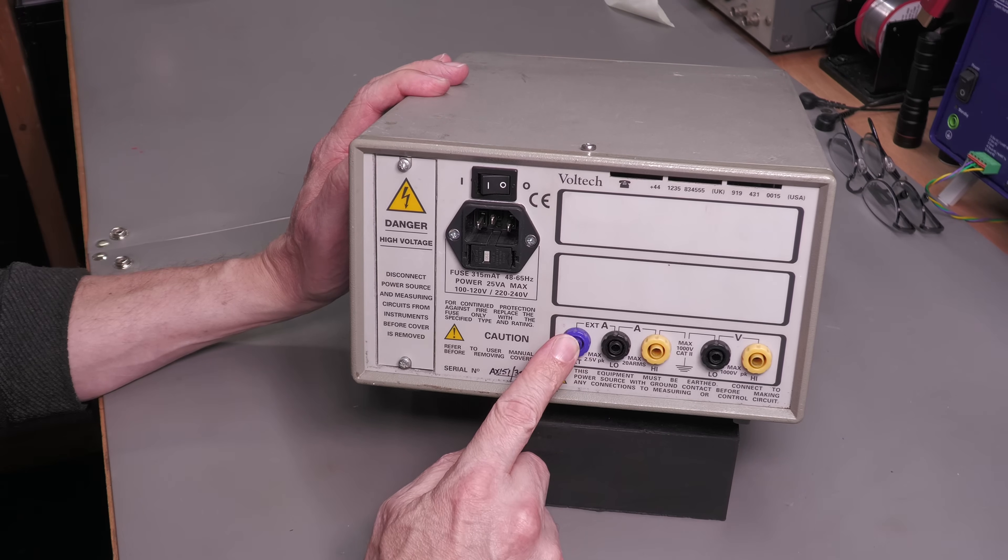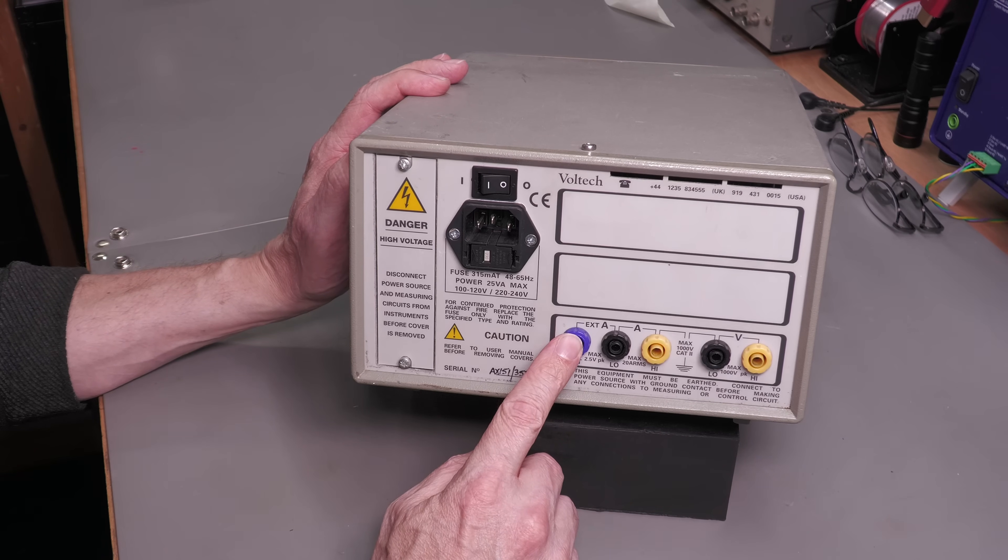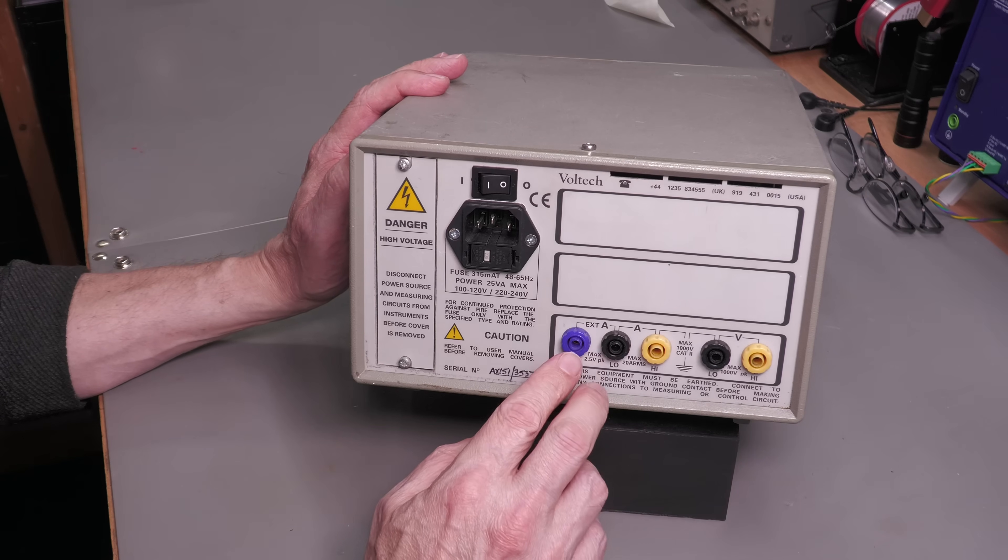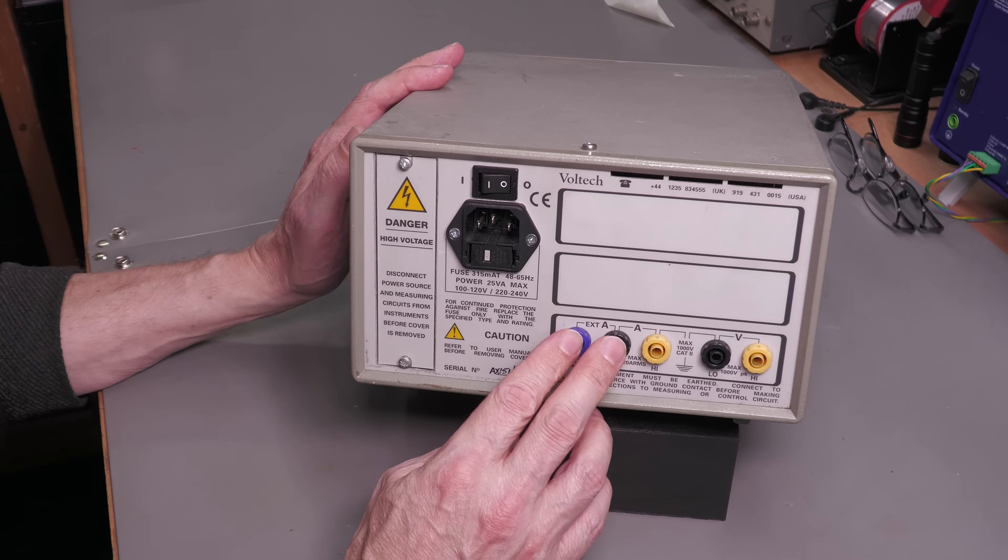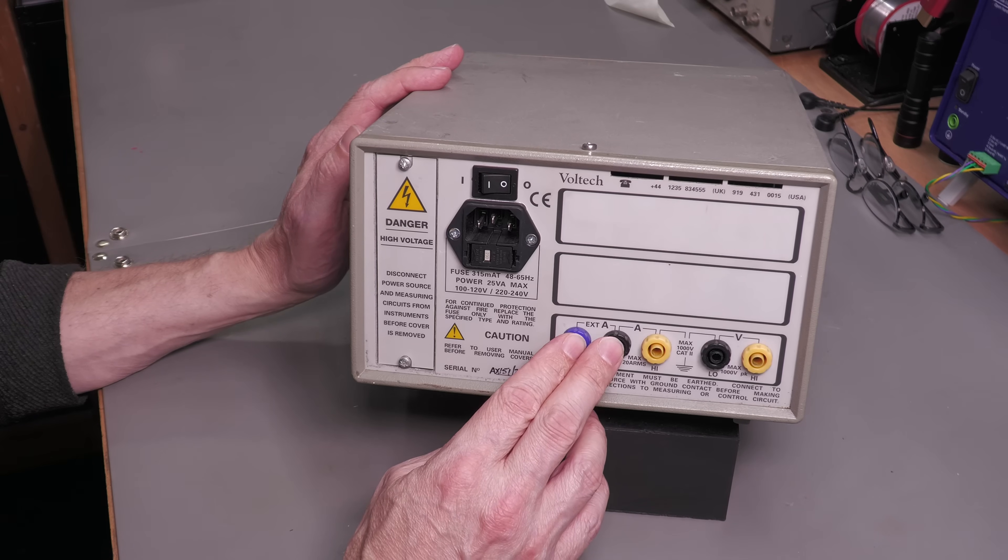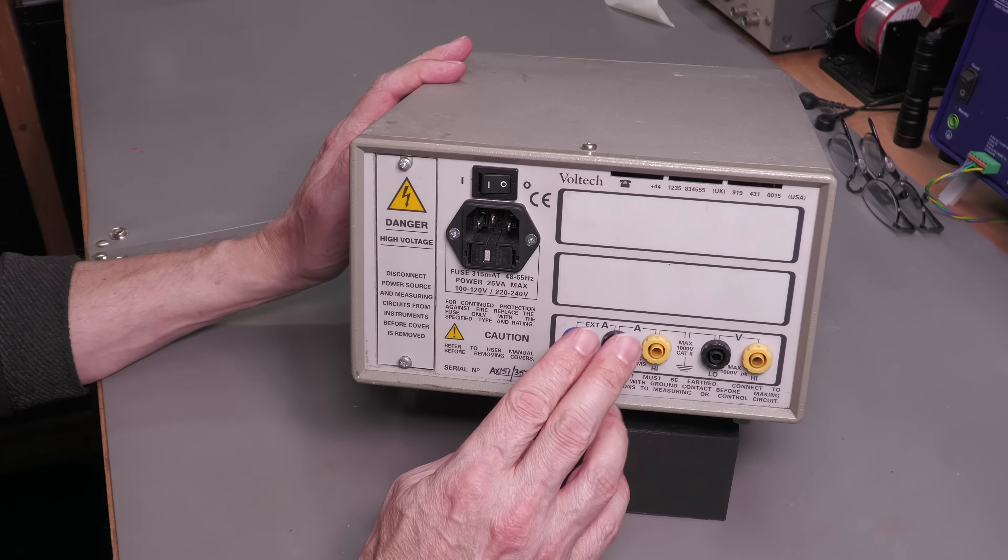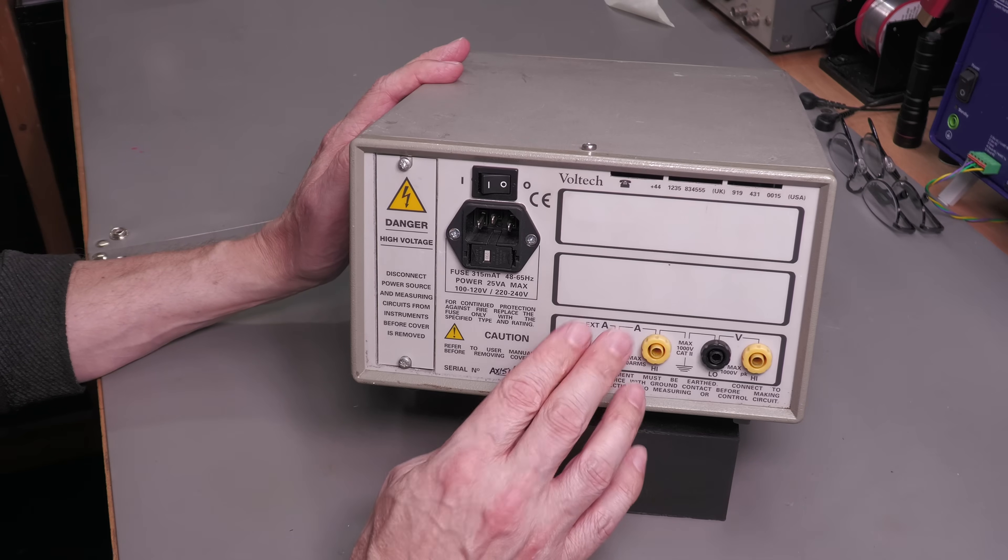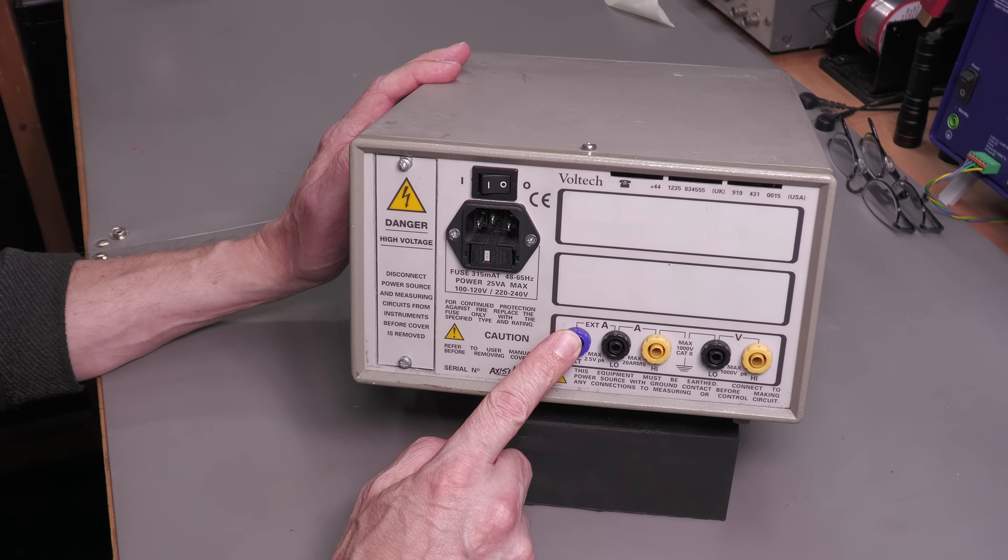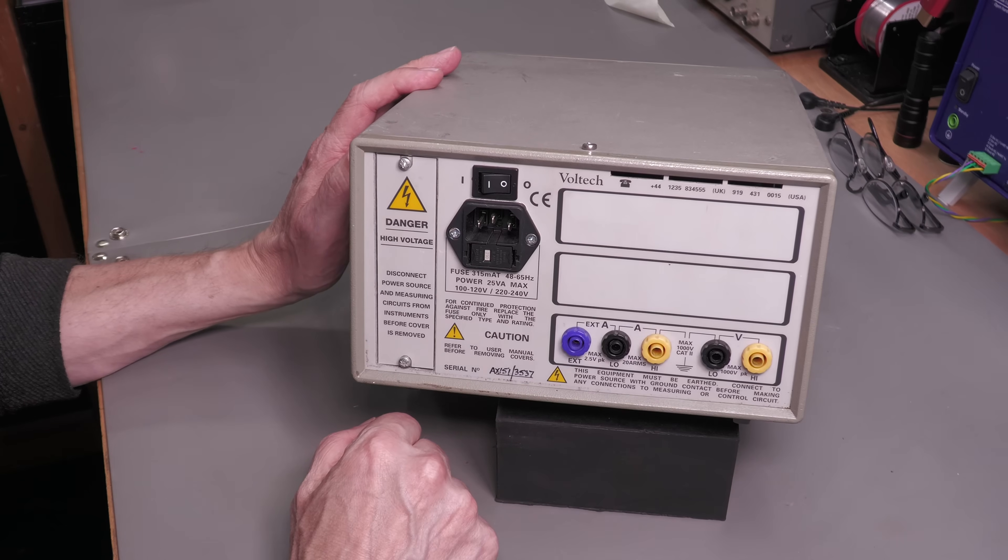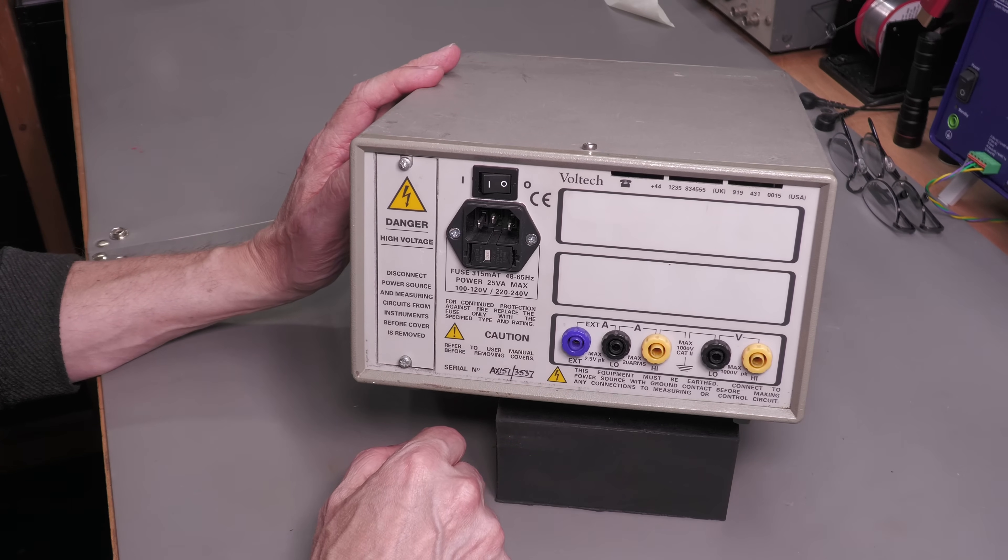This connection here is in the case of an external shunt, and this is actually a voltage input. It's a millivolt per amp input, and the default scaling is 100 millivolts per amp, but I believe that's adjustable. I don't actually use this blue input here. So let's tear down the unit, let's have a look inside.